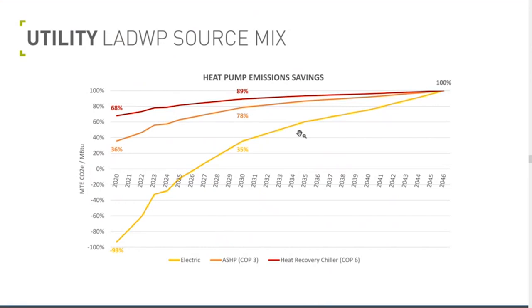This graph shows if you use these systems, either electric resistance, an air source heat pump which has about an efficiency of a COP of 3, or 300% efficiency, or a heat recovery chiller with about 600% efficiency that generates both heating and cooling, this shows your actual emissions savings from reducing electricity use over the life of that equipment. That equipment will last about 20 to 25 years, probably more for electric resistance. But you'll see a lot of that benefit early on because of the composition of our electricity within the state.